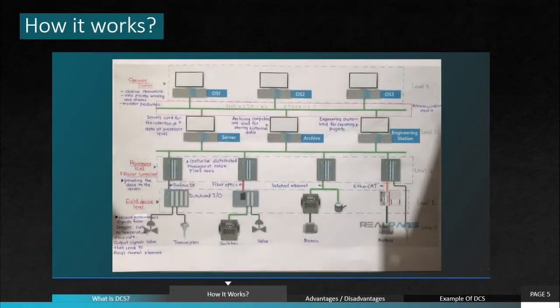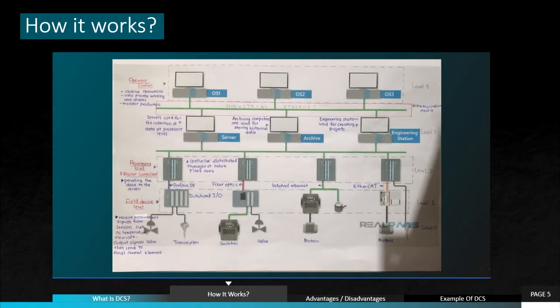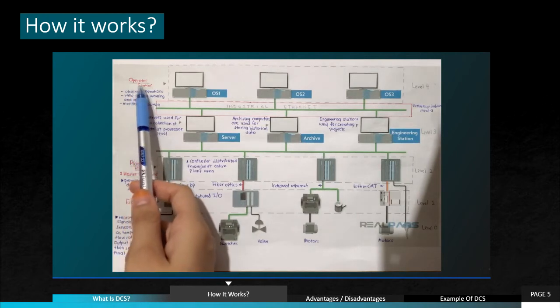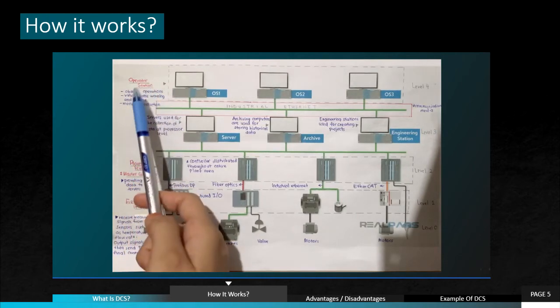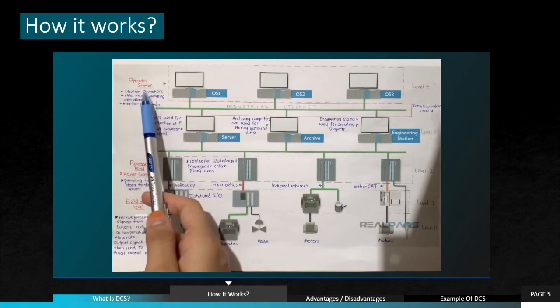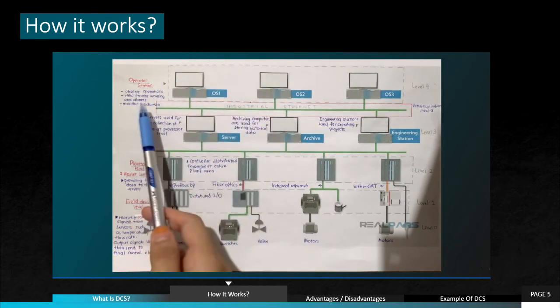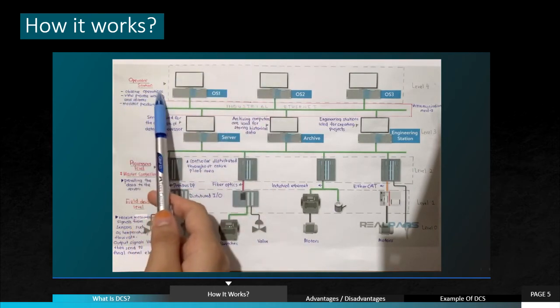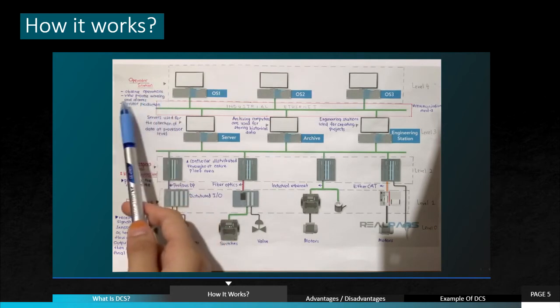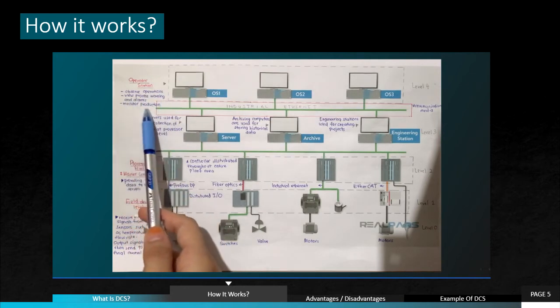Okay, now we're going to look at how this system works. Basically, in this DCS system, we have 4 basic elements. We're going to start from the operator station first. Basically, this operator station is the heart of the system because this is the one that observes the operation, views process warnings and alarms, and also monitors the production.